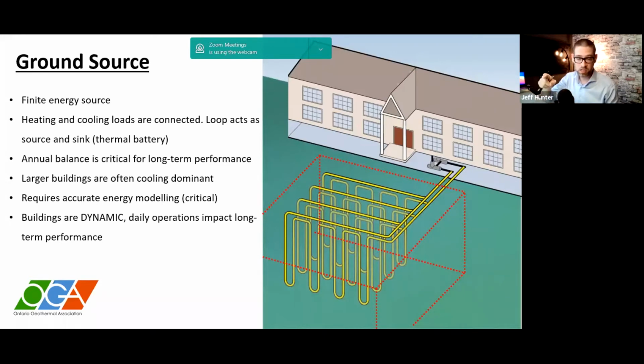So we need to be modeling the thermal performance of the loop, but also very accurately modeling the building performance. And that offers us in the design phase the opportunity to iterate and choose our mechanical systems and our building systems wisely, to understand the impact of, say, a reflective roof or a green roof, or changing solar heat gain coefficient values of the glazing. All that stuff will inevitably impact the energy in and energy out on the ground loop.